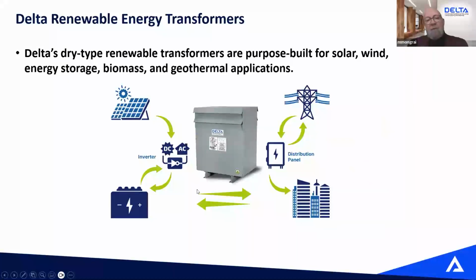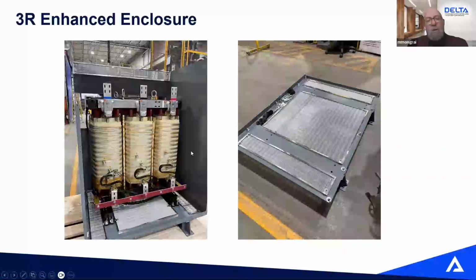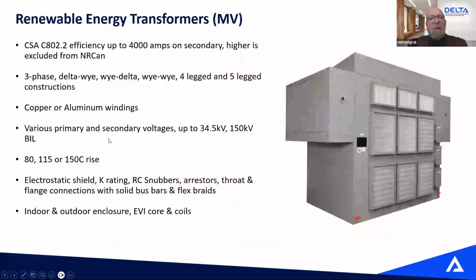the air to cool the transformer will be sucked in by the bottom here and will be exhausted at the top. So what we do in those cases to bring the transformer to an enhanced feature, we put aluminum mesh filters at the bottom where the cold air goes in, and at the top we put those filters again. Those filters will prevent the ingress of snow, rodents, debris. So it's a more rugged option for, I would say, our Canadian type of environment when you deal with outdoor type of installations.